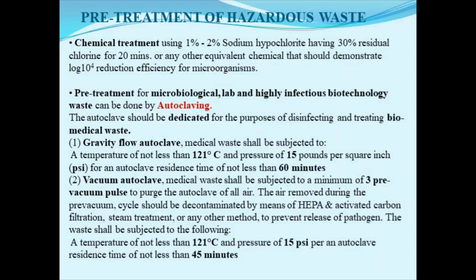One is the clean autoclave for sterilizing the media, and the holding time of that is usually 15 to 20 minutes. And another autoclave, that is the discard autoclave, should be used for pre-treating the biomedical waste, usually the microbiology, biotechnological waste and the blood bags. For that autoclave, we are usually using the gravity flow autoclaves, and the holding time for that is 60 minutes. So gravity flow autoclaves are mostly used in the laboratories.